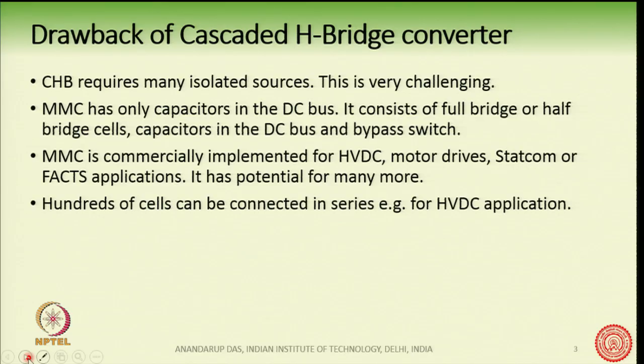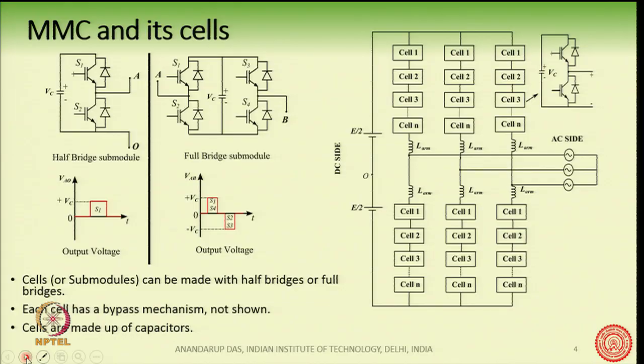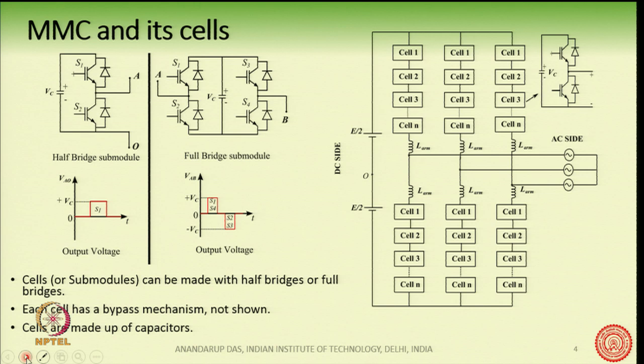In cascaded H-bridge we have seen cells connected in series, but when we talk about HVDC applications for which MMC is very suitable, we are talking about hundreds of cells connected in series. For example, at ±400 kV and 800 MW HVDC, we can connect hundreds of cells in cascade. The concept of modularity and scalability is very much applicable for MMC.